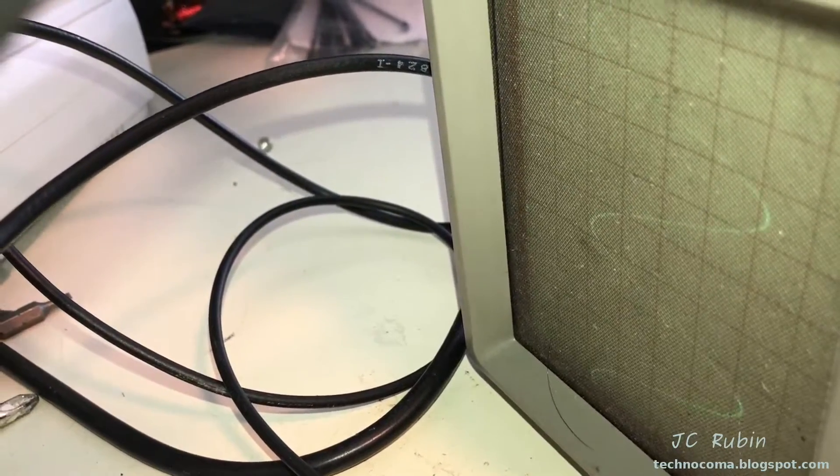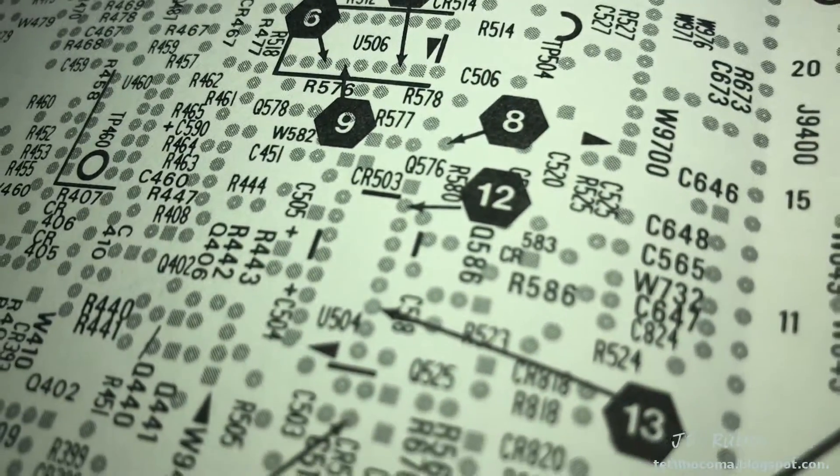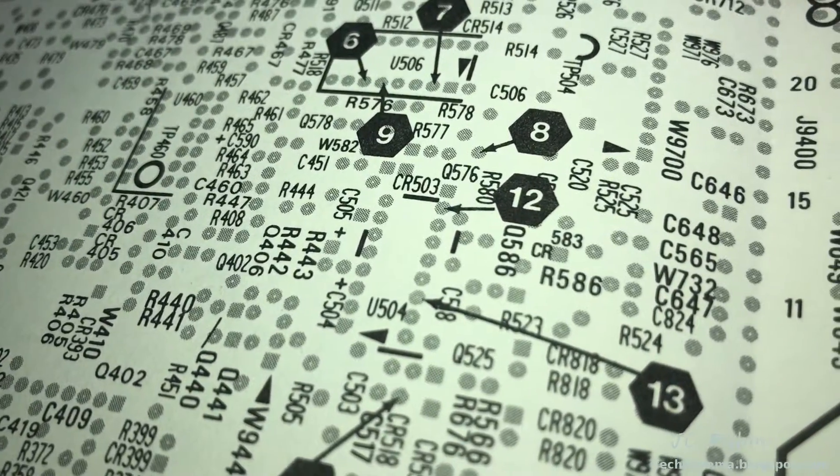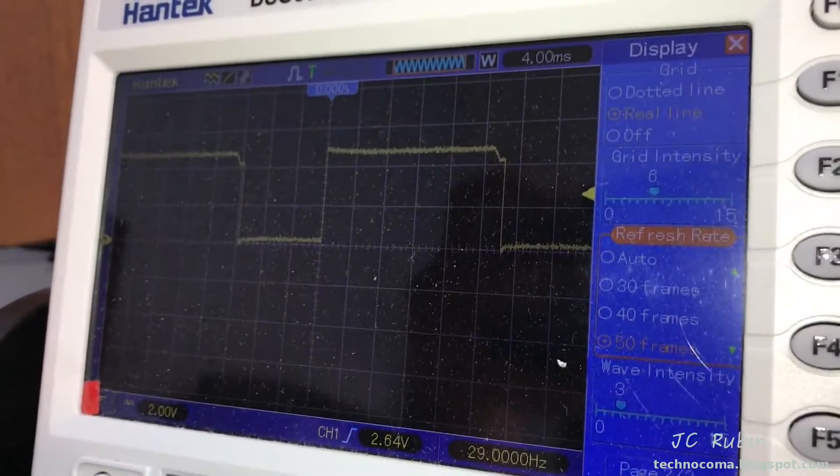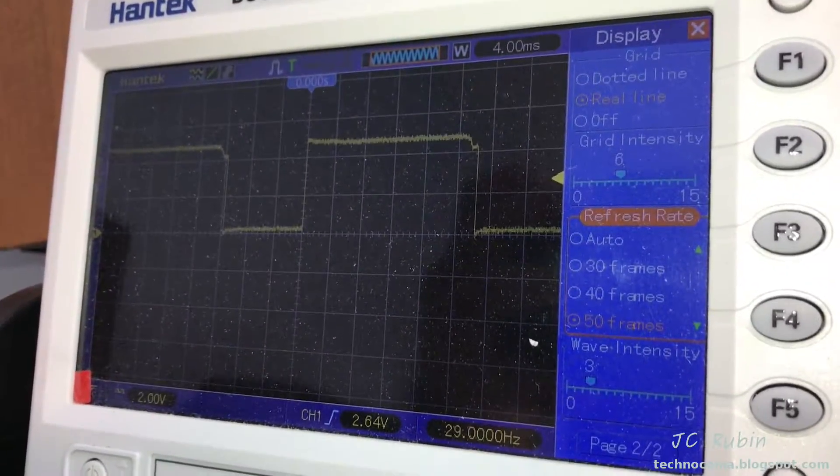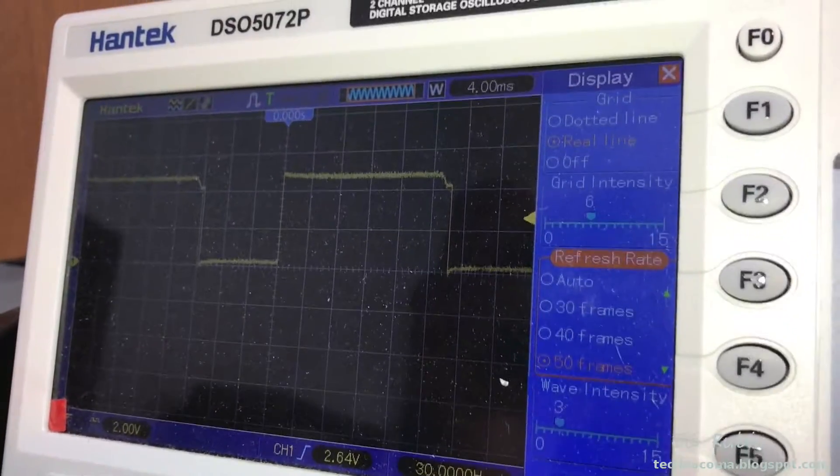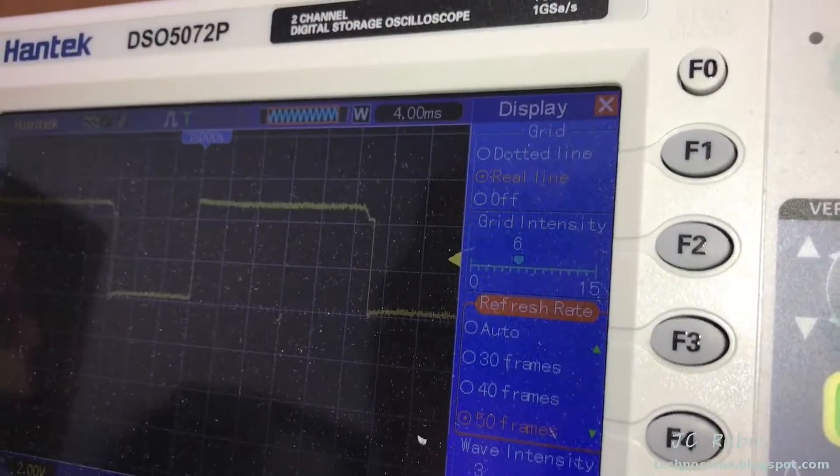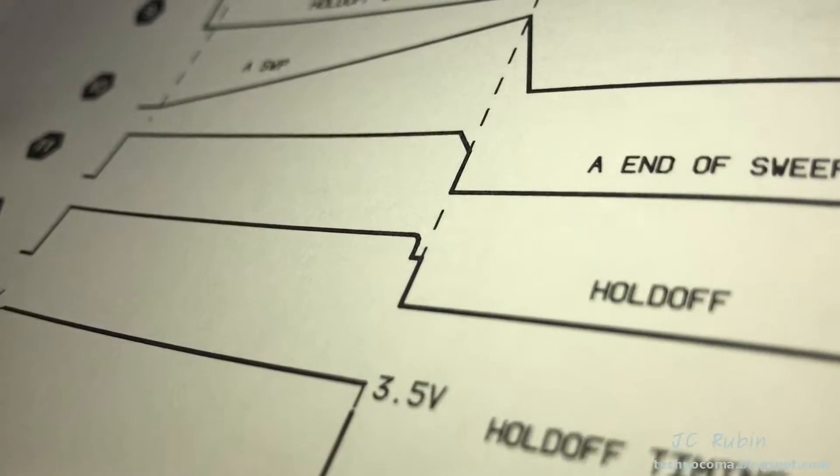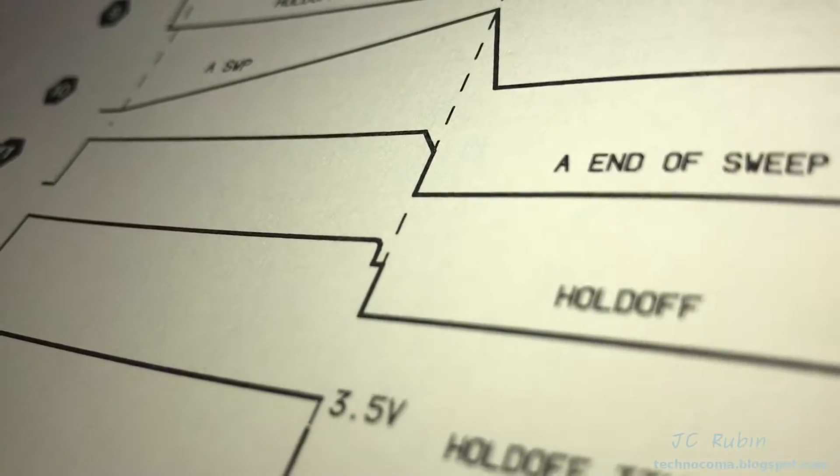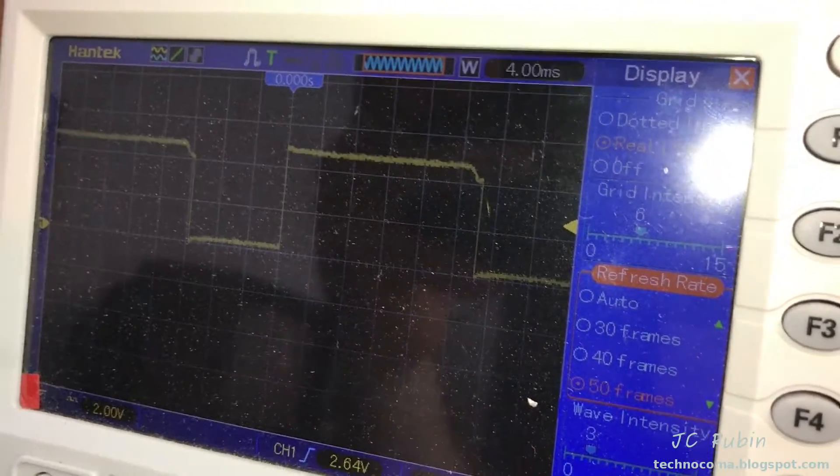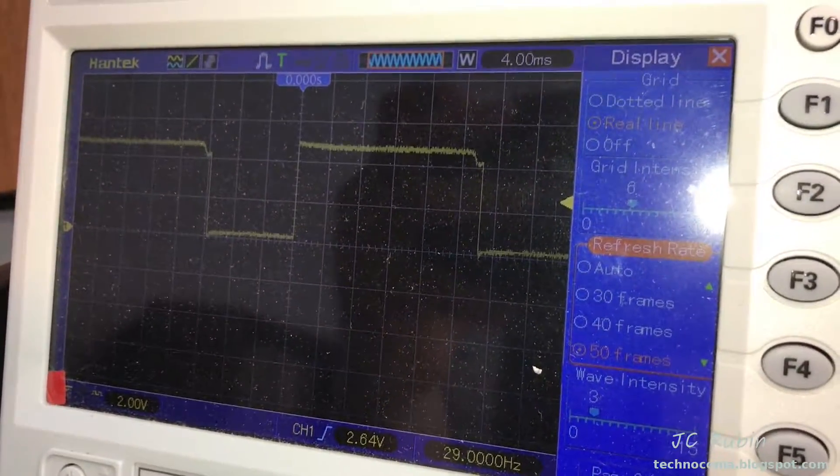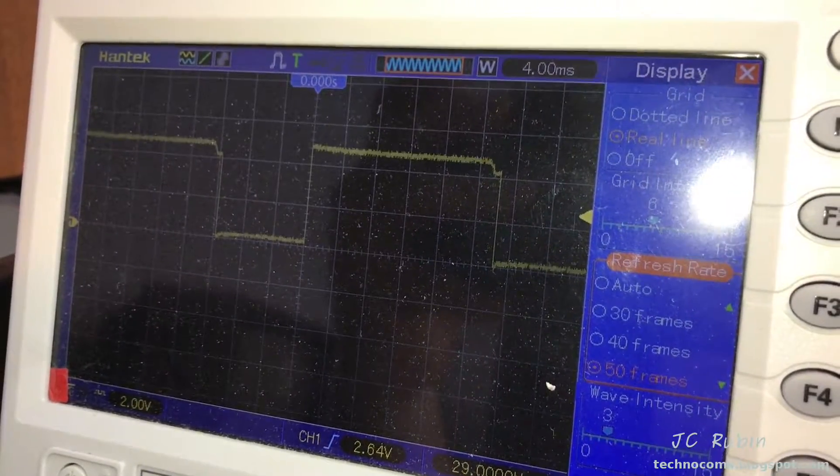I'm going to move on. Number 12 is the top right pin CR503. This test point number 12 is almost hand-drawn right out of the textbook. We could see the square wave with a different duty cycle and that little notch right at the end of the square wave. If we look in the book you could see that little notch right there on hold-off. It's absolutely perfect. I'm going to say number 12 is good too.